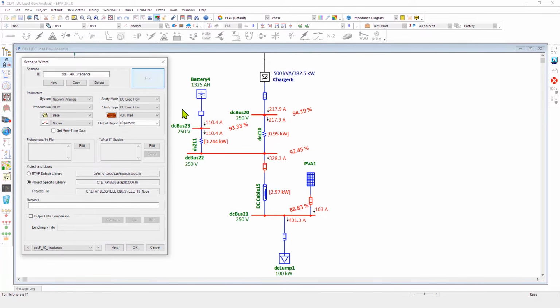The next case we will run is 40% irradiance. Here we can observe that the PV array power increases to more than double its value. The voltage improves, and we can see that based on the BMS setting, the battery is no longer discharging and the power is purely compensated based on the contribution between the battery rectifier as well as the PV array.